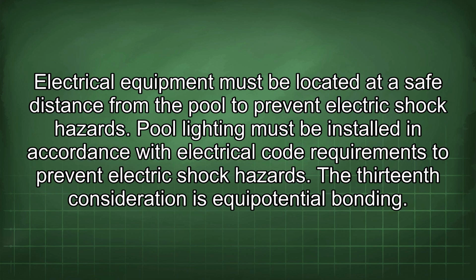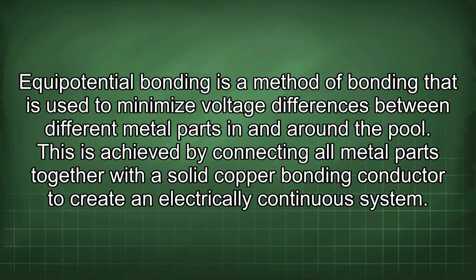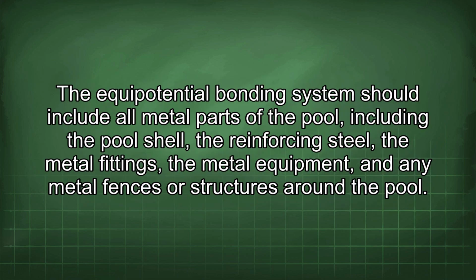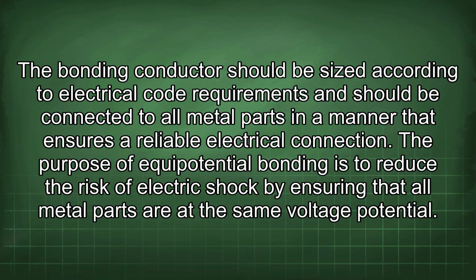The 13th consideration is equipotential bonding. Equipotential bonding is a method of bonding that is used to minimize voltage differences between different metal parts in and around the pool. This is achieved by connecting all metal parts together with a solid copper bonding conductor to create an electrically continuous system. The equipotential bonding system should include all metal parts of the pool, including the pool shell, the reinforcing steel, the metal fittings, the metal equipment, and any metal fences or structures around the pool. The bonding conductor should be sized according to electrical code requirements and should be connected to all metal parts in a manner that ensures a reliable electrical connection.